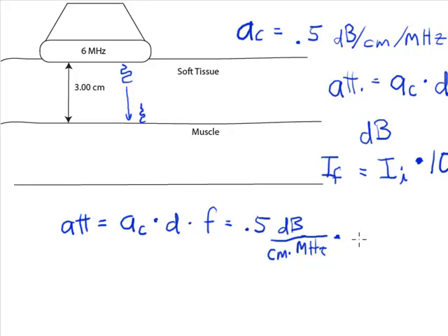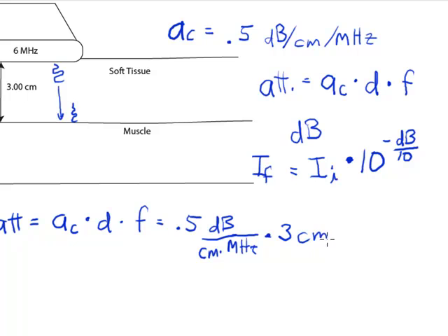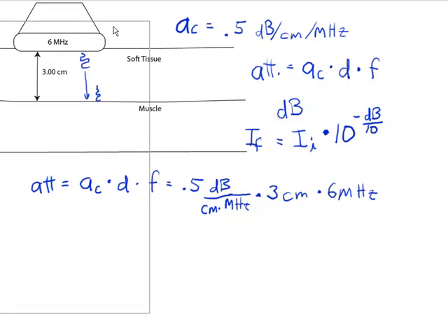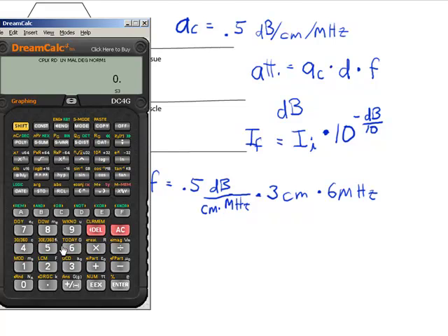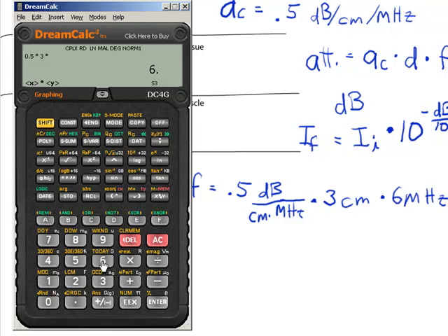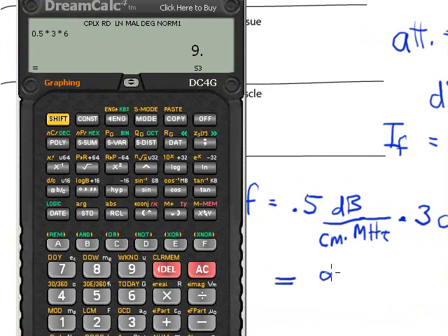And then I'm going to multiply by the distance, which is 3 cm in this case, and the frequency, which is 6 MHz. And so I'll bring in the calculator. Even though this one is probably easy enough, we didn't need to use the calculator. So I have 0.5 times 3 times 6. And that's equal to 9 dB of attenuation.